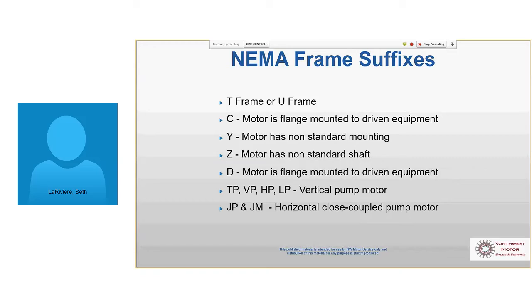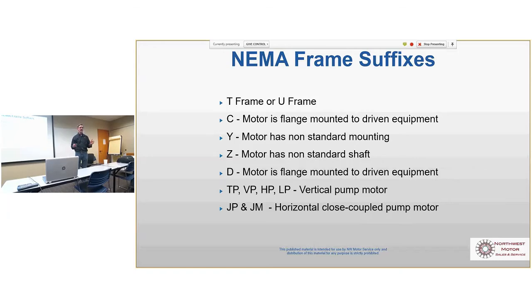I want to physically see the application, see where the motor goes, what's weird about it, is there room, is there a space limitation, is it a double shaft? Because people use Y, even though Z is the non-standard shaft designation, I've seen Y used for double shafted motors. I don't know why, but people do. So there's all kinds of different Ys. They can mean anything. A D flange is a lot like a C face, except there's bolts that go through the flange. It's a small difference. And these are all vertical frame designations.